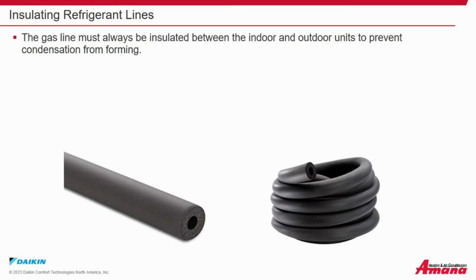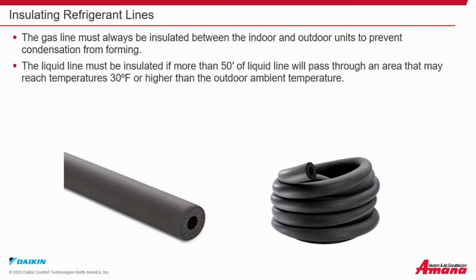Insulating refrigerant lines. The gas line must always be insulated between the indoor and the outdoor units to prevent condensation from forming. The liquid line must be insulated if more than 50 feet of liquid line will pass through an area that may reach temperatures 30 degrees Fahrenheit or higher than outdoor ambient temperature.